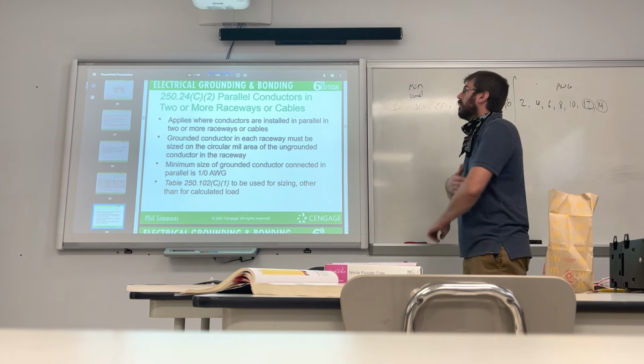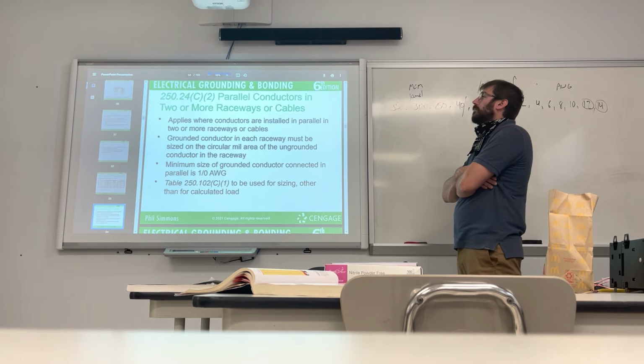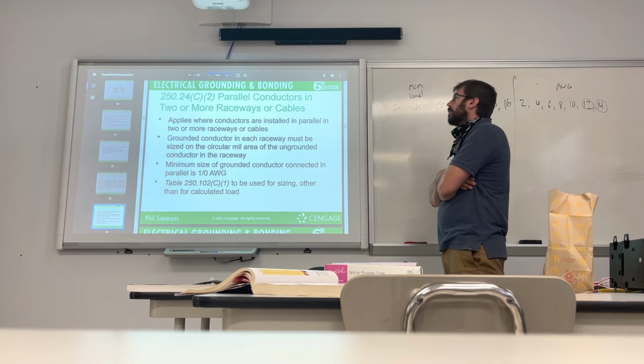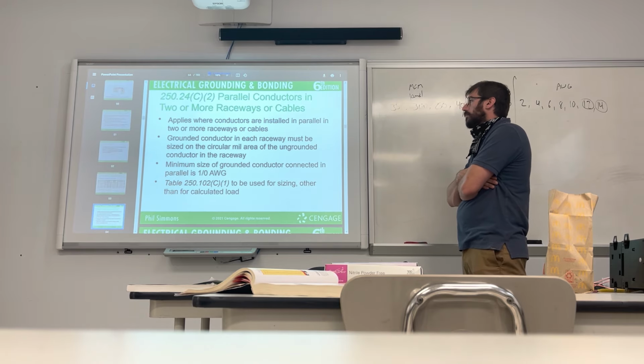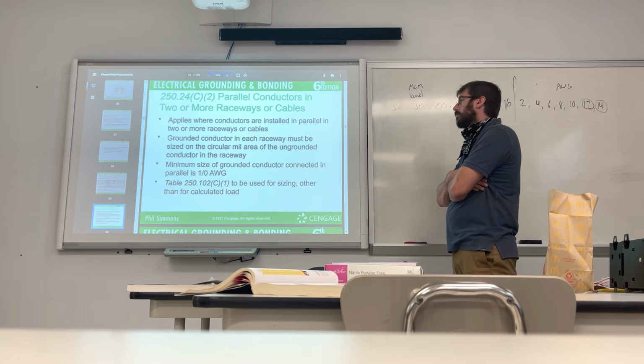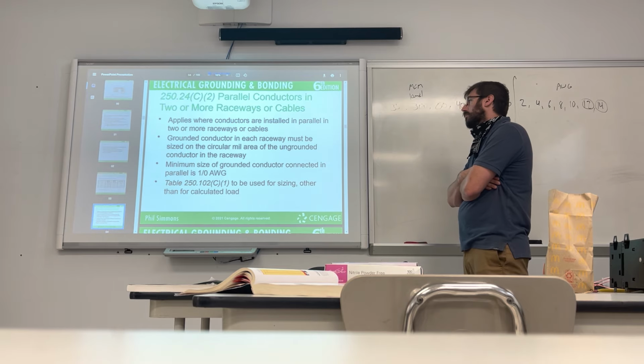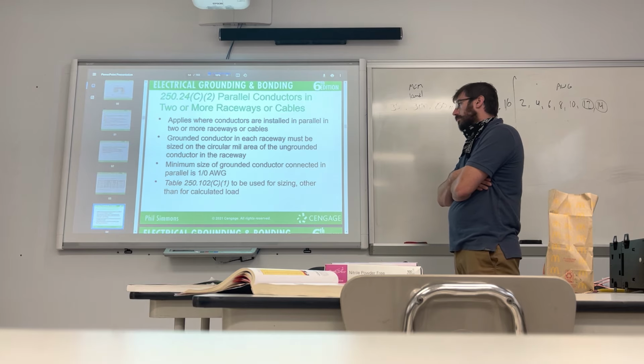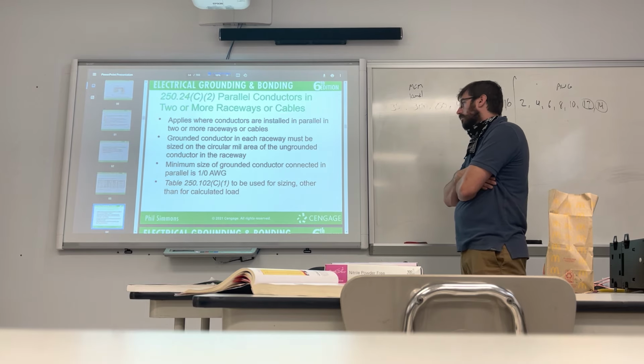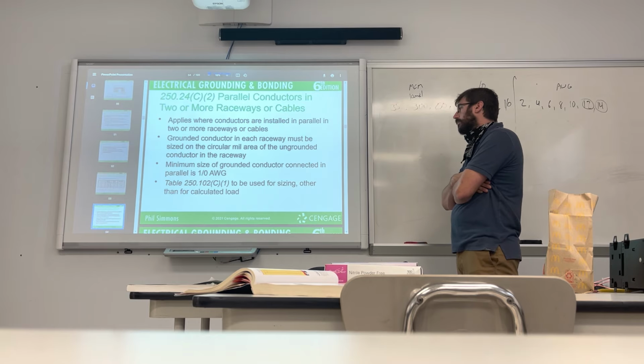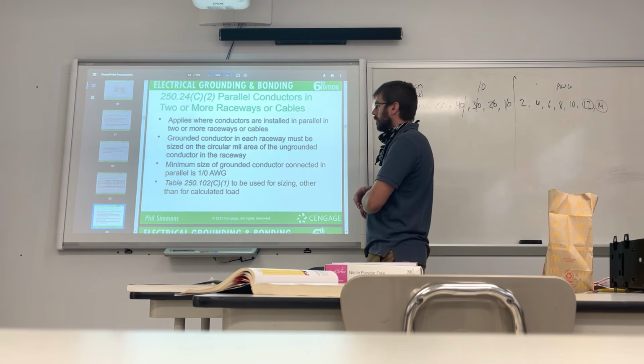Parallel conductors in two or more raceways or cables. Applies when conductors are installed in parallel in two or more raceways or cables. The grounded conductor in each raceway must be sized on the circular mil area of the ungrounded conductor in the raceway. The minimum size of a grounded conductor connected in parallel is 1/0 AWG. Table 250.102(C)(1) is to be used for sizing, other than for calculated load.